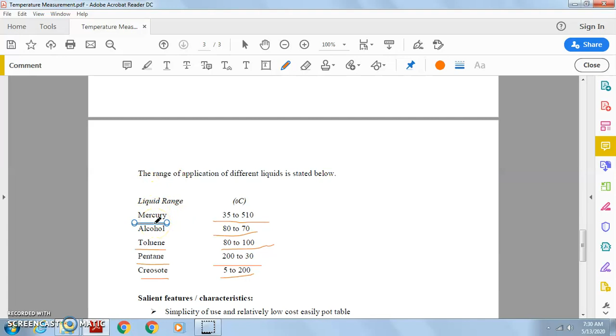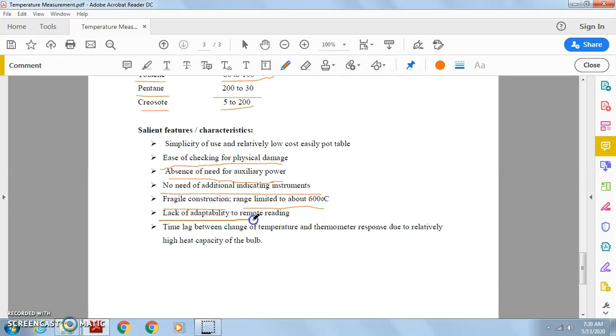Okay, this temperature range. So salient features: simplicity of use and relatively low cost, easily portable, and ease of checking the physical damage, absence of need of auxiliary power, no need of additional indicator instrument, fragile construction, range limited to about 600 degrees centigrade, lack of adaptability to remote reading, time lag between change of temperature and thermometer response due to relatively high heat capacity of the bulb. That means within the salient features we notice there are advantages and also some disadvantages of this particular type of thermometer.